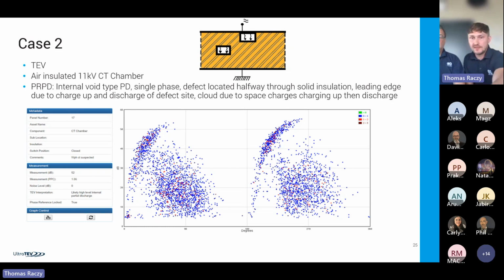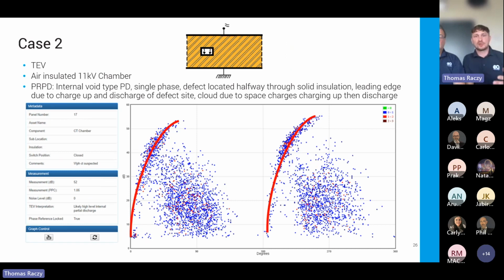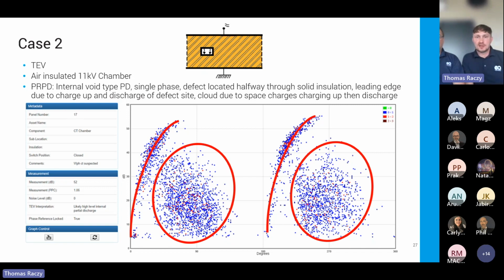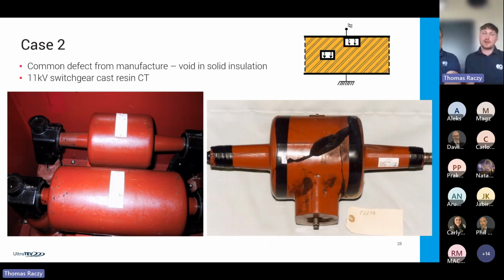So we've got a very well-defined leading edge. That initial discharge is defined almost by the characteristic geometry of the void itself, and it creates quite a high level of PD. What follows after that initial leading edge is a more sparse clustering of the signals, and this is typically the after effects, the semiconductor effects, and all the gas byproducts within the cavity after the initial discharge, which create the perfect environment for more discharges to still occur on the rising or falling edge of the sine wave. And this is the actual source of discharge.